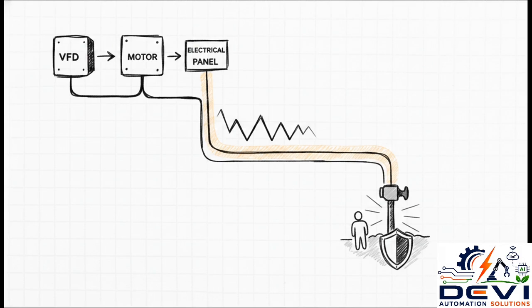You know, VFDs are notoriously noisy devices. They generate a ton of high-frequency electrical noise. A proper shield ground dramatically reduces this noise, which keeps your sensitive control signals clean and accurate.